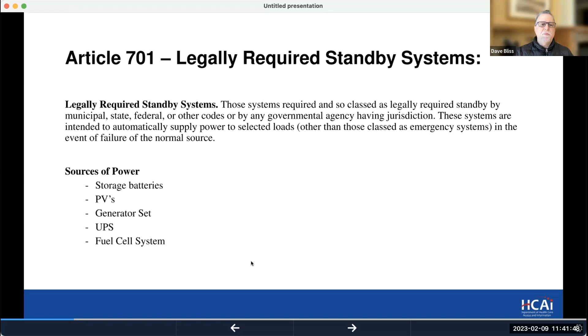So as John talked about, this is the conventional appearance of what we see in any skilled nursing facility. You almost certainly have, if you have the appropriate level of acuity, some backup generation set up, but it would be very unusual for that generator to cover all loads throughout the entire facility. In other words, it's likely you have certain boards within your facility that are intentionally, in effect, electrically disabled when the utility is no longer available, and those aren't functional.